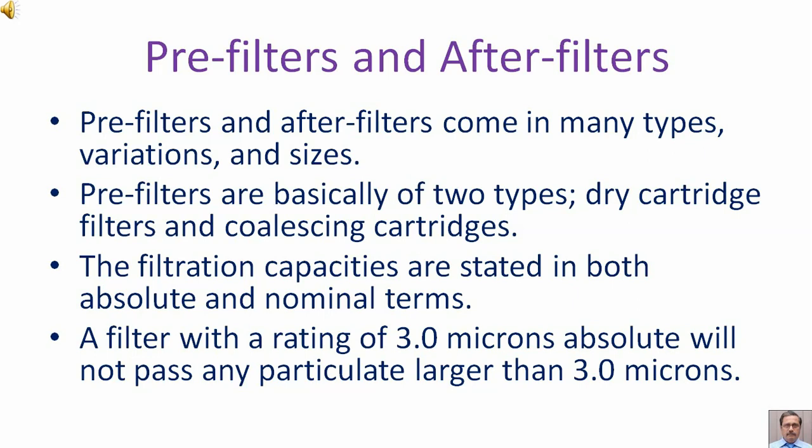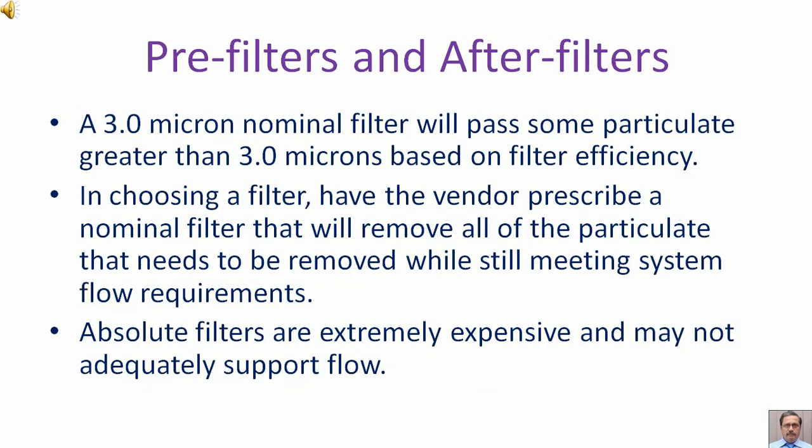Filter capacities are stated in both absolute and nominal terms. A filter with a rating of 3 microns absolute will not pass any particulate larger than 3 microns. A 3 micron nominal filter is rated based on filter efficiency. In choosing a filter, have the vendor prescribe a nominal filter that will remove all of the particulate that needs to be removed while still meeting system flow requirements. Absolute filters are extremely expensive and may not adequately support flow.